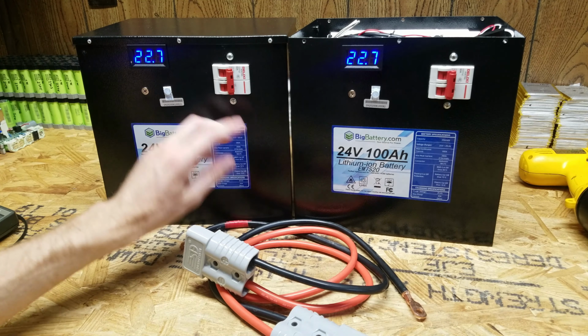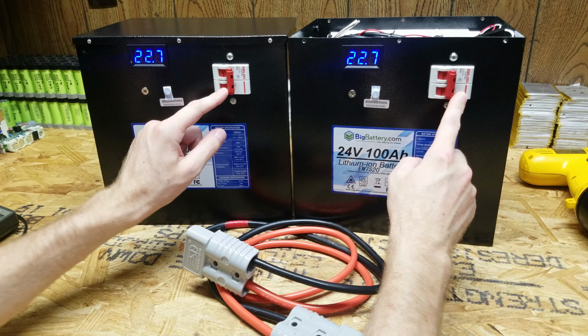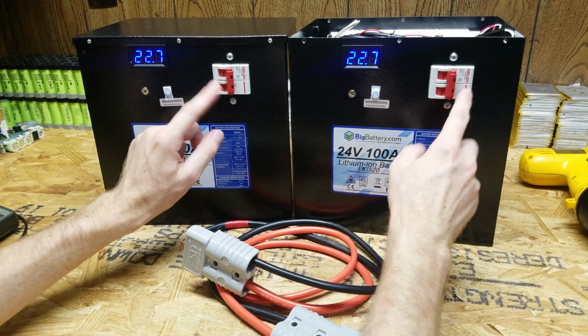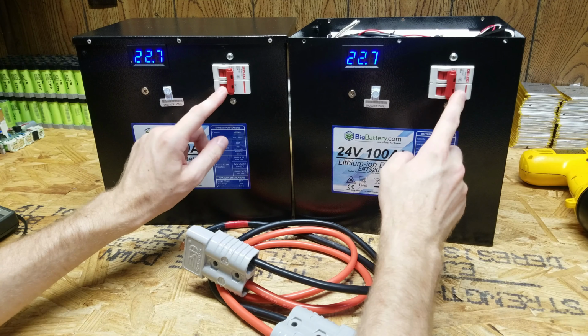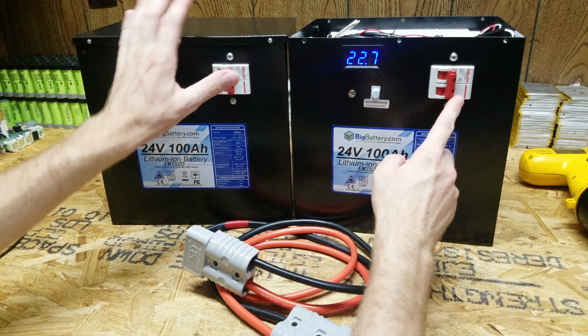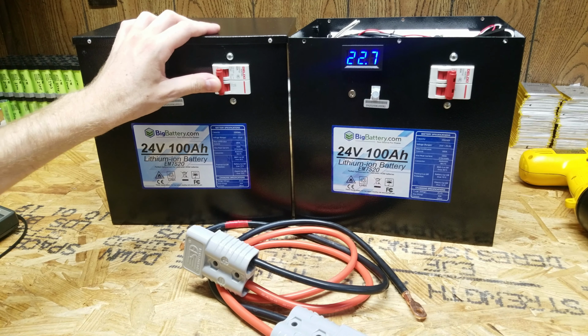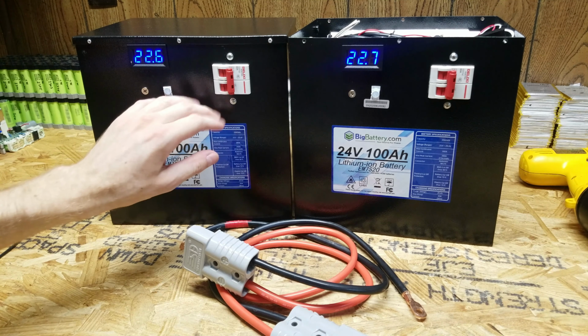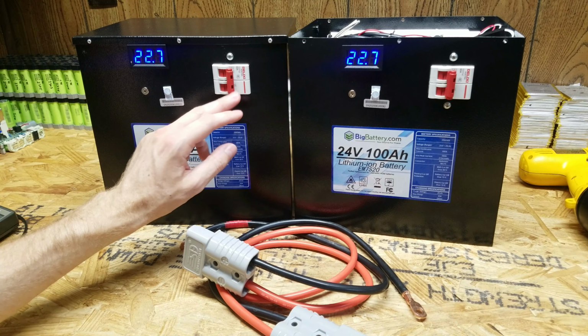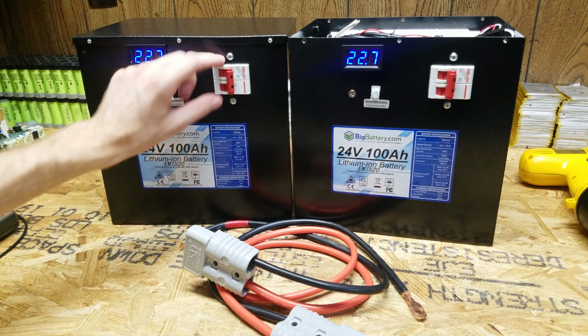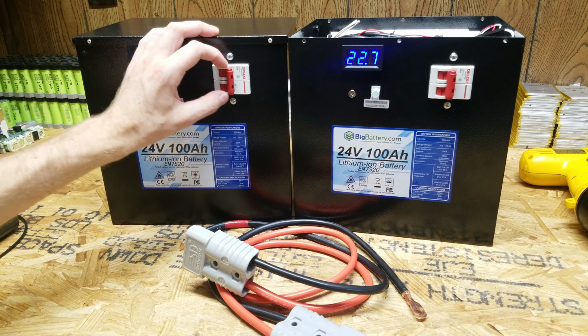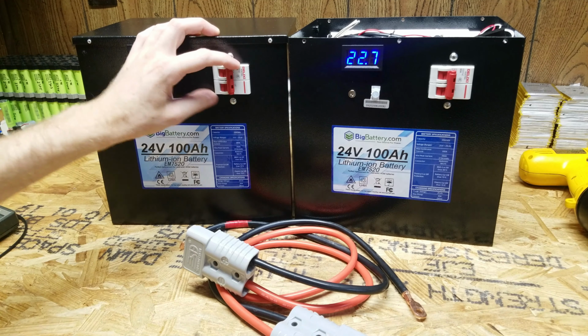The only thing I don't like are these circuit breakers. We really should not be using 2 poles of the same circuit breaker to double the amount of current going through it. I would have much rather seen a proper 125 amp breaker installed in here, a single pole or double pole with the negative going through it. I think the biggest problem when you parallel 2 poles like this is you can't guarantee the same amount of current is going through both poles.